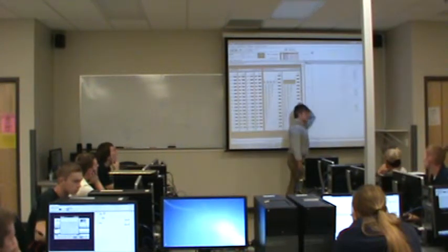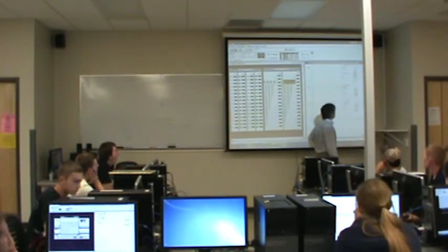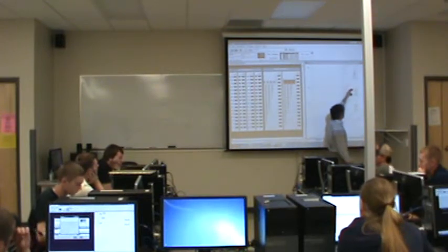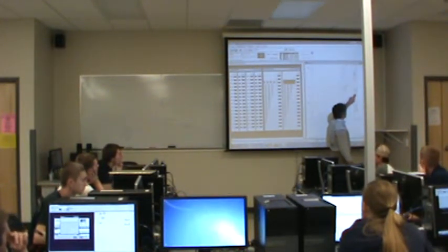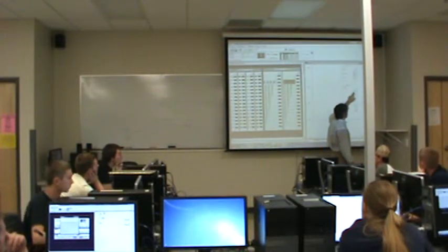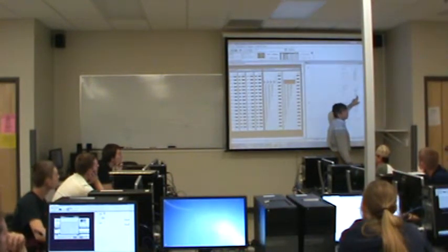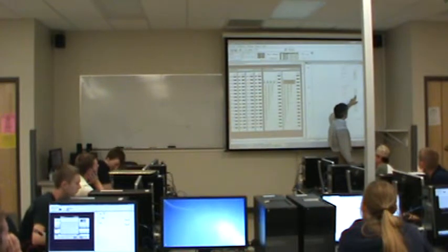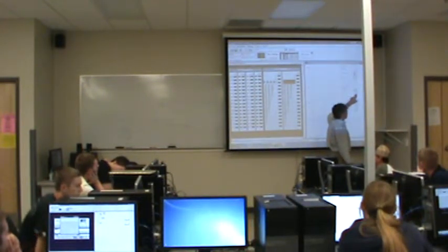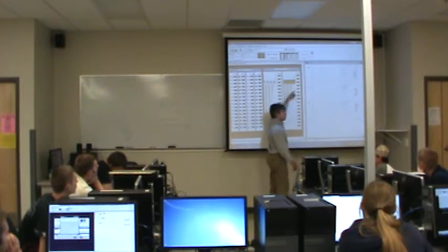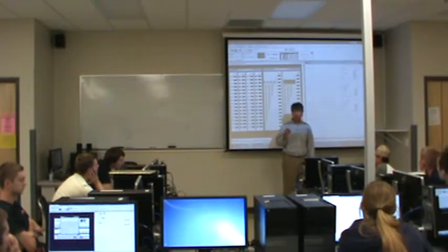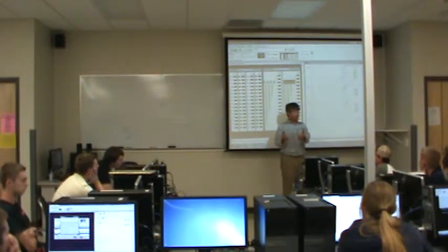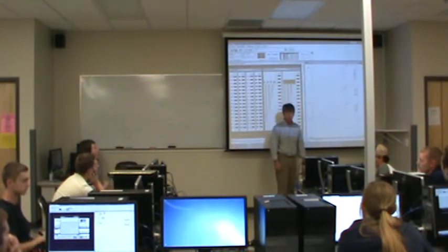You might be scratching your head a little bit and saying, yeah, but what's going on here? Because the move instruction looks at this address and copies the data into memory here, so I'd expect to see 2330 here and here, because this is displaying what is actually going out to output 6. But what's going out to output 6 is 9009, yet what's being shown is 2330. We have to be very careful. It's a mistake to have 2 instructions trying to write the same output. That'll trip you up more than once in this class.